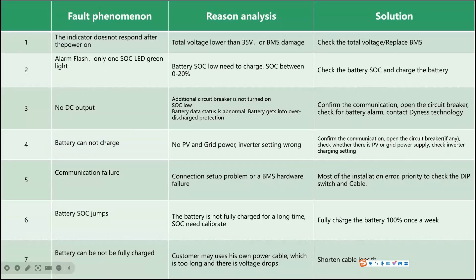And the battery cannot be fully charged. This case I actually met 3 days ago, a customer on an island who has 6 batteries connected in parallel, but he reports some of the batteries cannot be fully charged. After checking, I found that the customer used their own power cable, because they paralleled so many batteries, but the cable is too long. When the power cable is too long, there is voltage drop, so the charging voltage the BMS requires is not enough. So in this case, I had the installer shorten the cable, and then the problem was fixed.